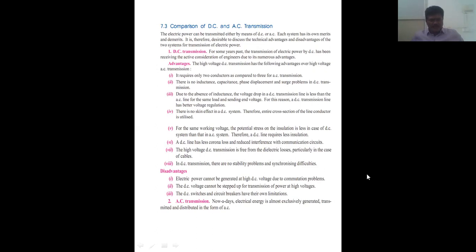There is no skin effect in DC system, therefore the entire cross-section of the line conductor is utilized. For the same working voltage, the dielectric stress in insulation is less in case of DC system than AC system, therefore a DC line requires less insulation. A DC line has less corona loss and reduced interference with communication circuits.